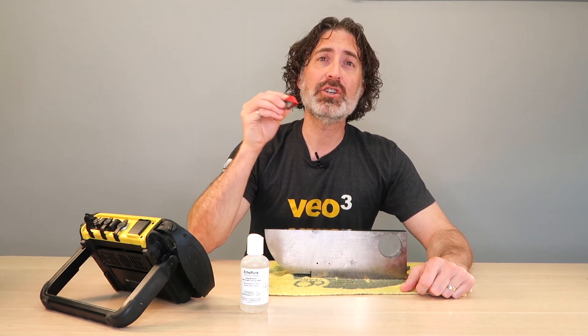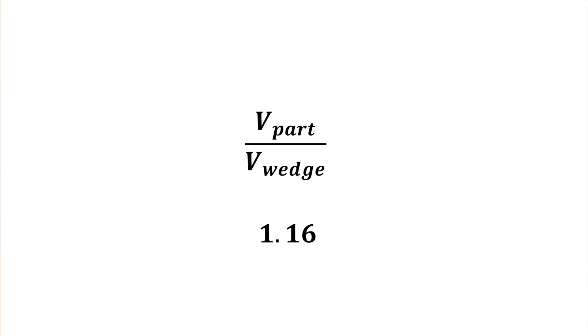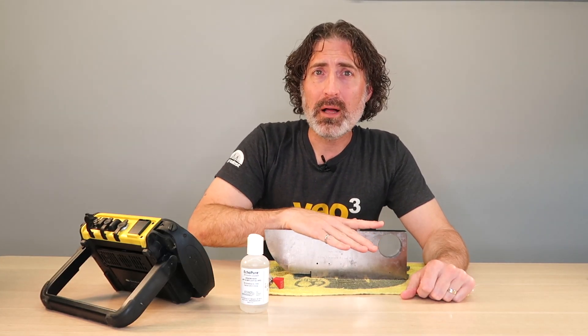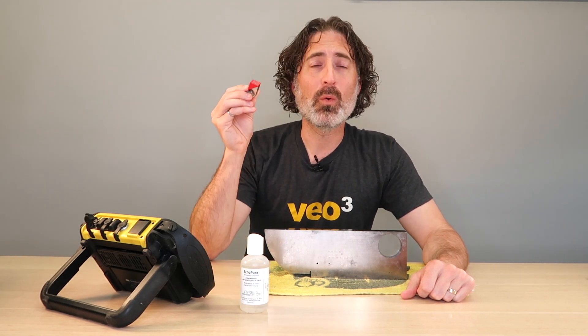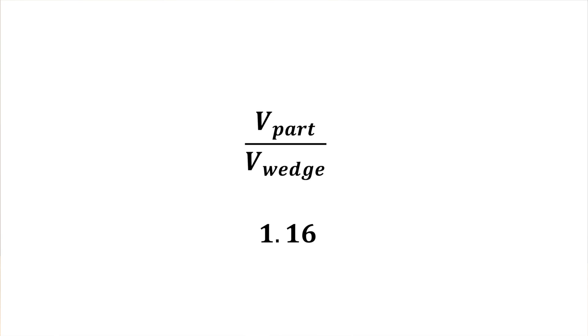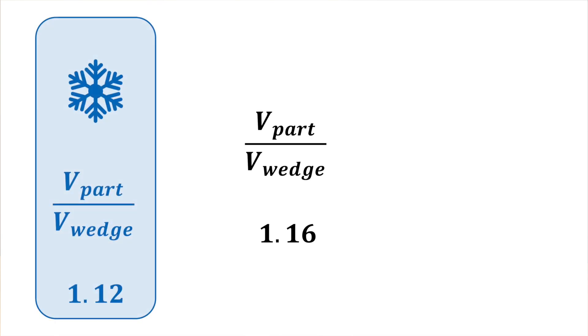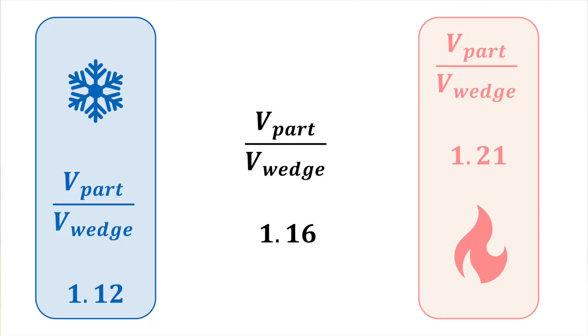At room temperature, the ratio between the longitudinal wave velocity in lucite and the shear wave velocity in steel is about 1.16. When the temperature goes down, the velocity of sound in steel goes up a little bit, but it goes up a lot more in the wedge. Since the wedge velocity is on the bottom of the fraction, that ratio value goes down — at minus 20, it ends up being about 1.12. On the other side, when we turn the heat way up to 60 degrees Celsius, velocity goes down a little in steel but a lot more in the wedge, so our ratio is 1.21.